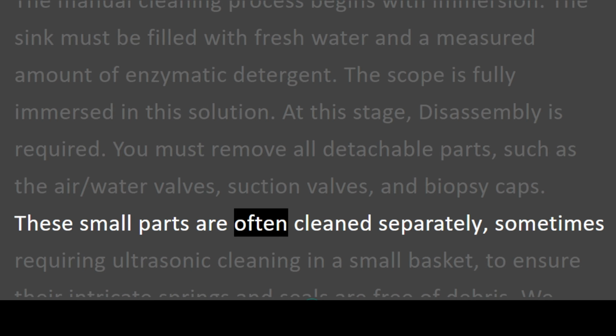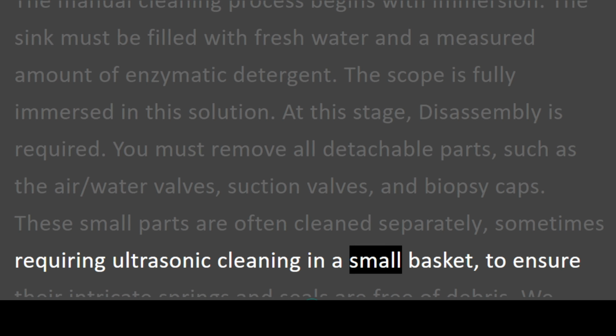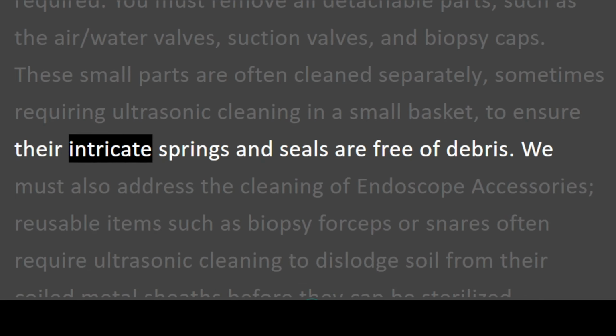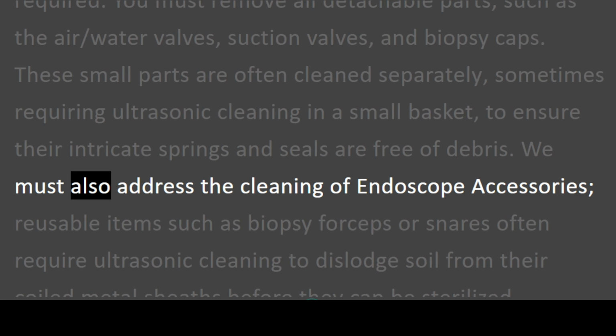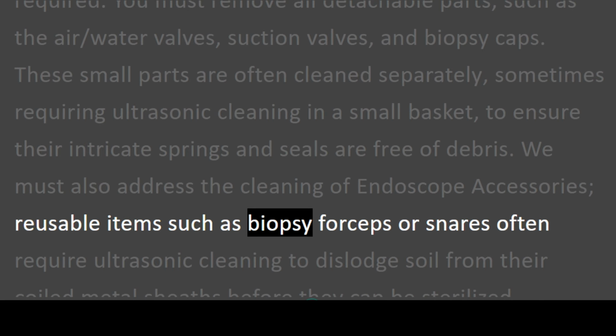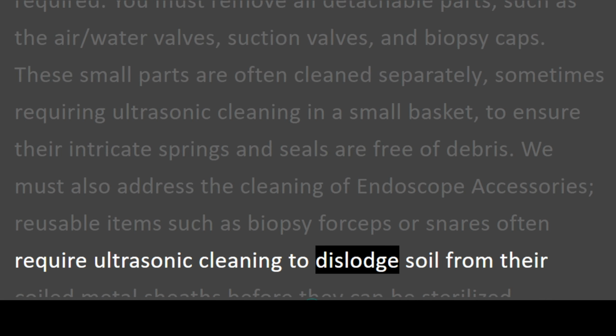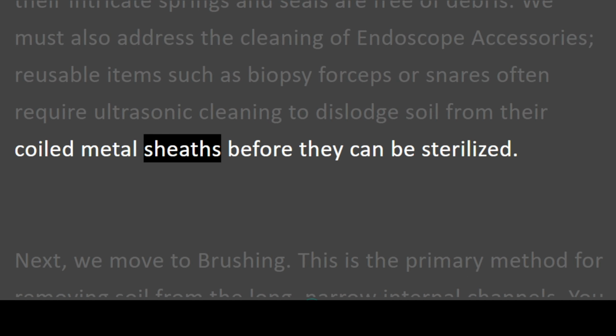These small parts are often cleaned separately, sometimes requiring ultrasonic cleaning in a small basket, to ensure their intricate springs and seals are free of debris. We must also address the cleaning of endoscope accessories. Reusable items such as biopsy forceps or snares often require ultrasonic cleaning to dislodge soil from their coiled metal sheaths before they can be sterilized.